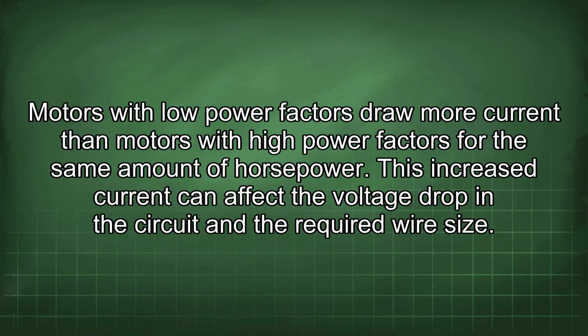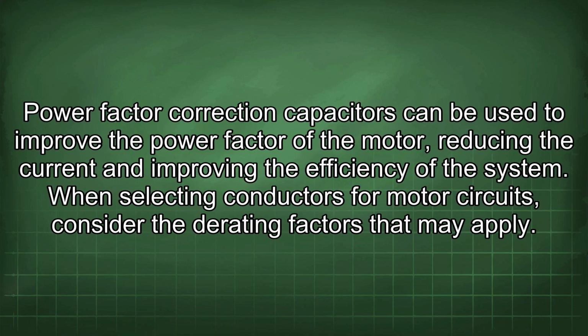Furthermore, the power factor of the motor can affect the current flowing in the circuit. Motors with low power factors draw more current than motors with high power factors for the same amount of horsepower. This increased current can affect the voltage drop in the circuit and the required wire size. Power factor correction capacitors can be used to improve the power factor of the motor, reducing the current and improving the efficiency of the system.